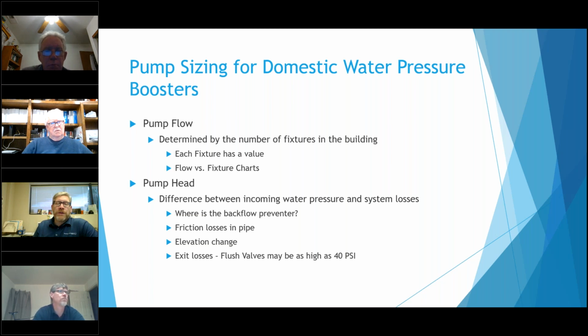Pump head, it's really, most of it's going to be your elevation change. You do have to worry about some of that friction loss in the pipe, but a lot of it's going to be elevation change and any exit losses through these flush valves and everything.